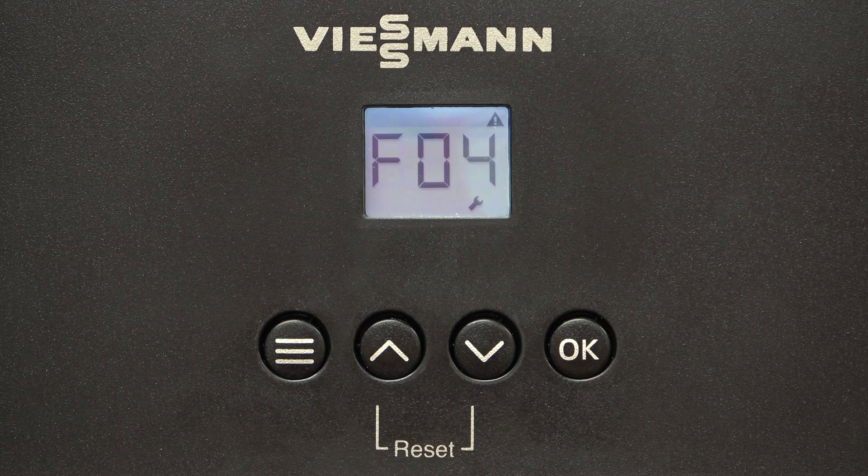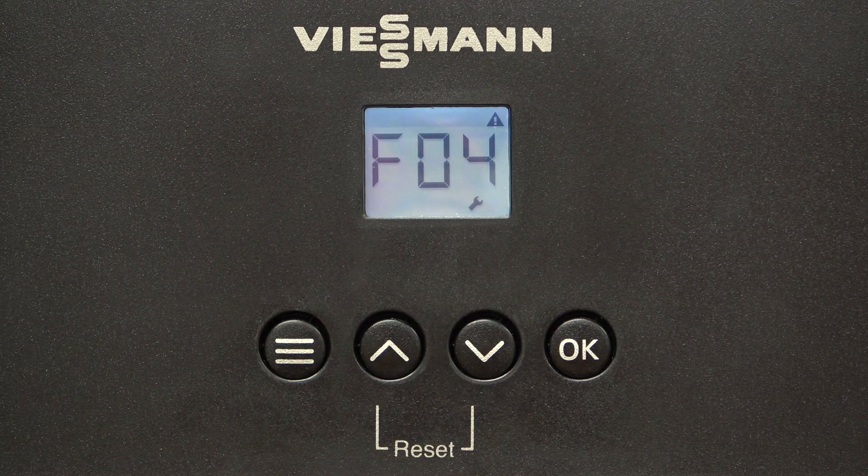To restart the test, press the up and down arrows for a minimum of 5 seconds. The flue test will start automatically and will be indicated by a flashing display. The device will attempt to ignite after the second minute, which will be indicated by a flame symbol in the display.